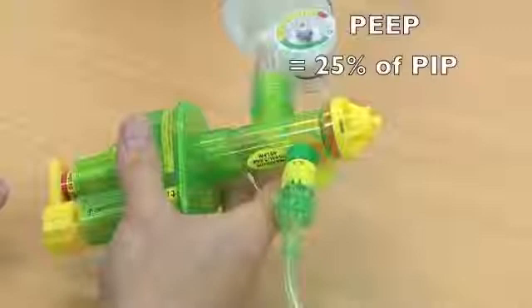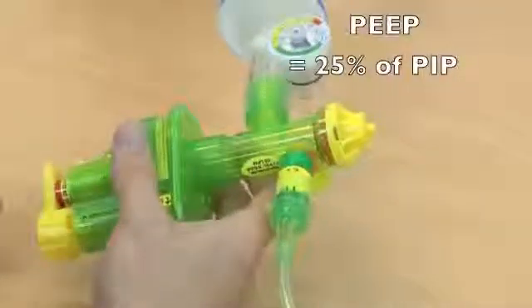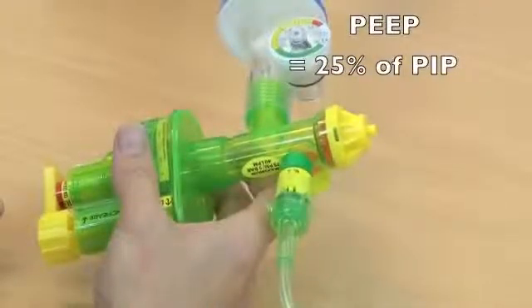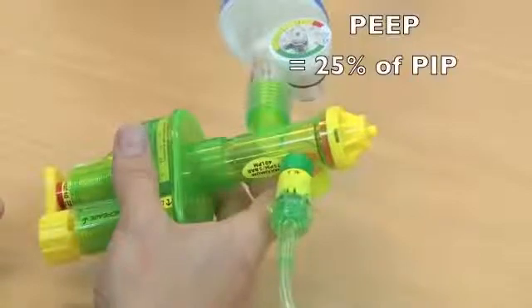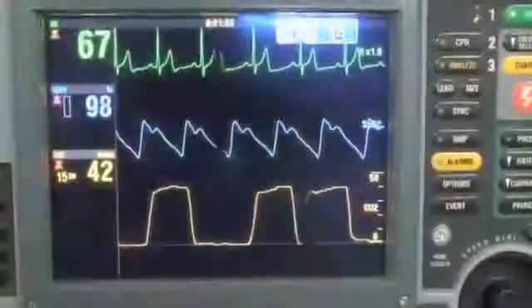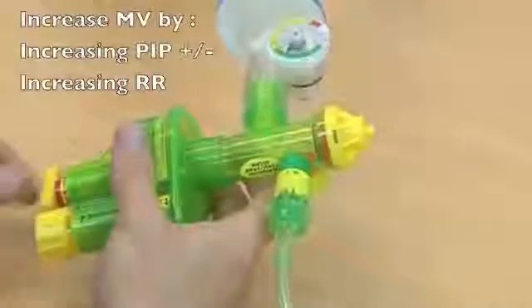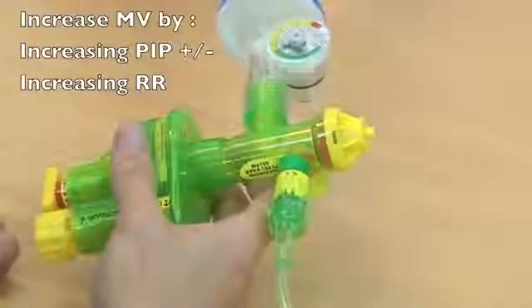The PEEP — positive end expiratory pressure — is automatically set at 25% of the PIP, so that if the PIP is 24, the PEEP will be 6. Tidal volumes are not directly measured on the SureVent 2, but we use end tidal CO2 and the respiratory rate as indicated on the patient monitor to adjust our settings. If the end tidal CO2 is rising and we wish to increase minute ventilation, we can either increase PIP, increase respiratory rate, or both.